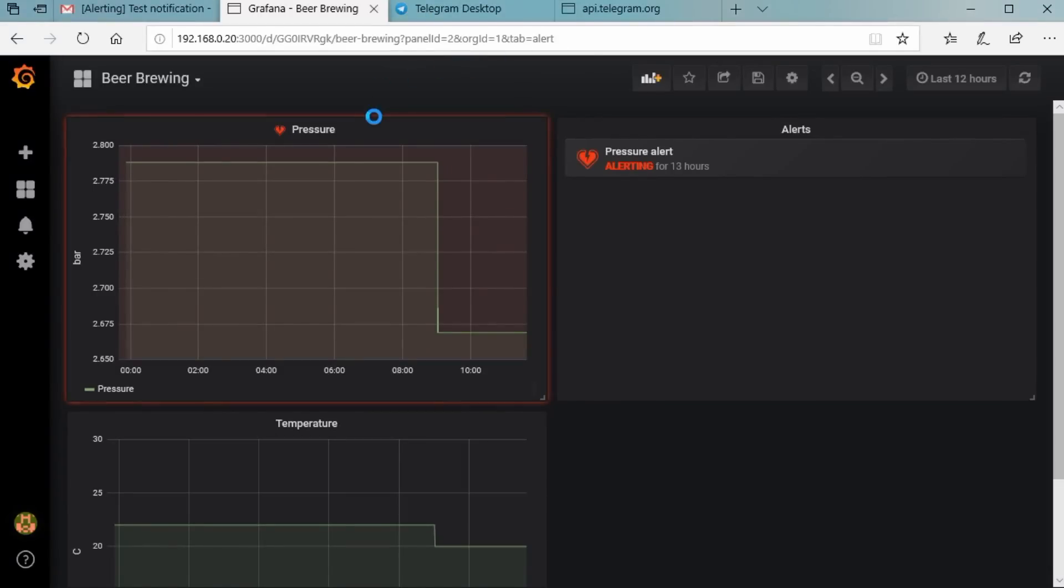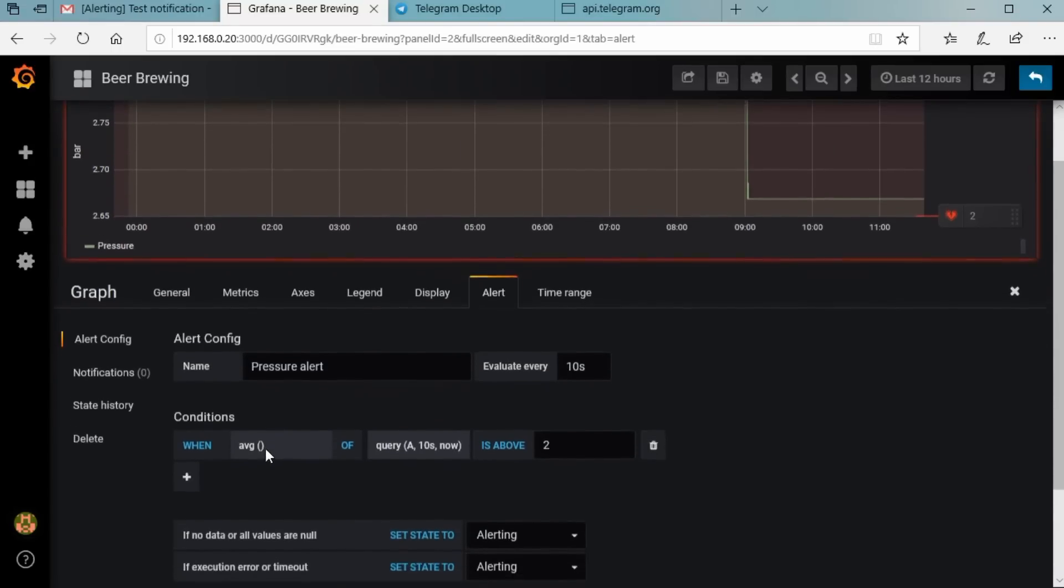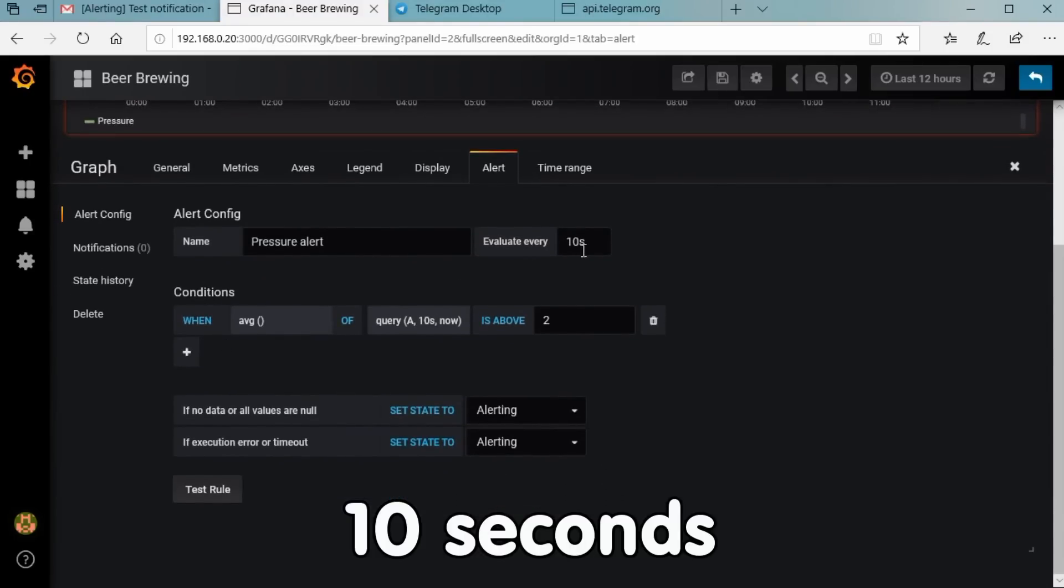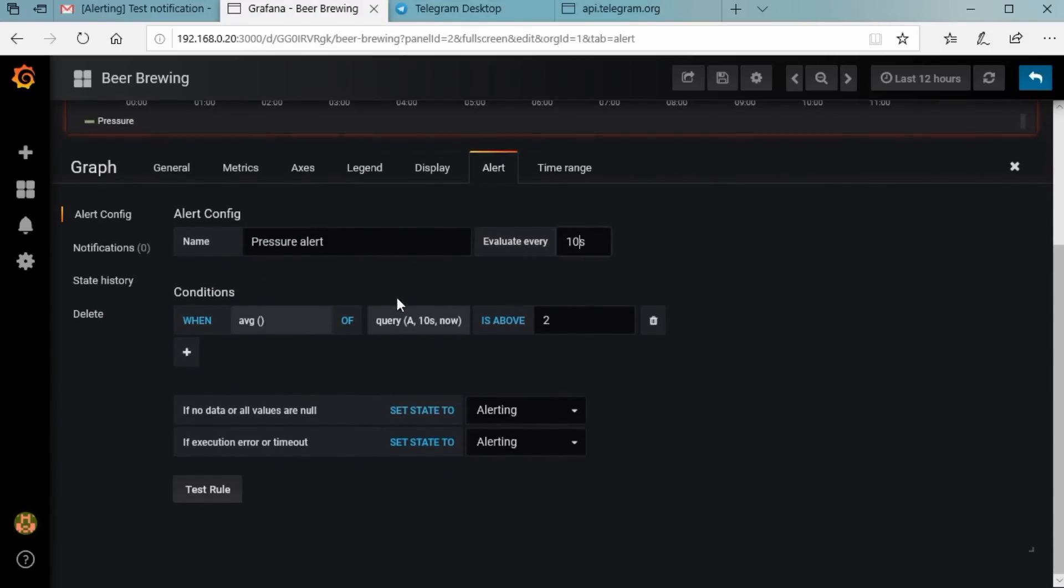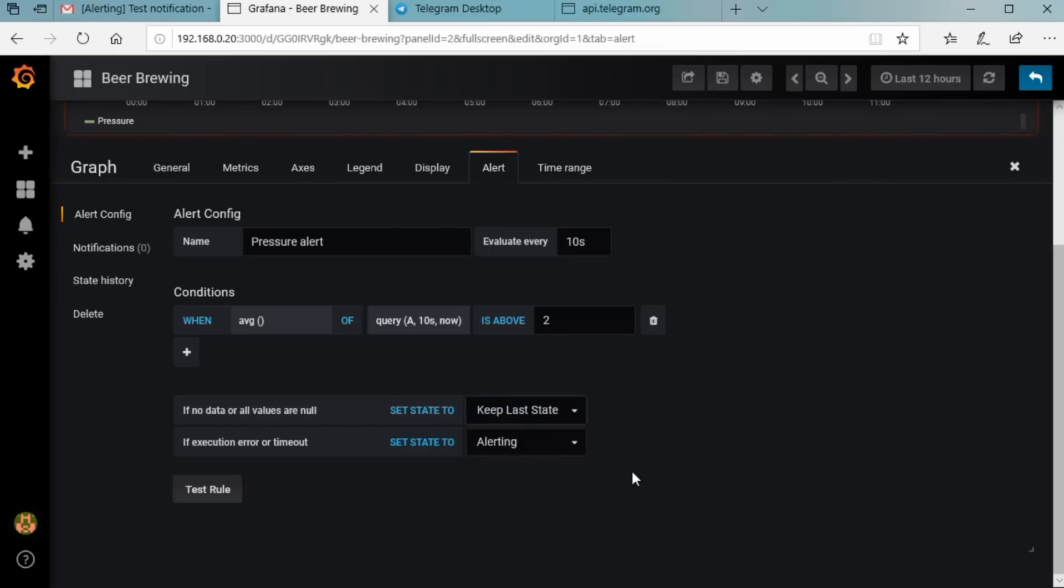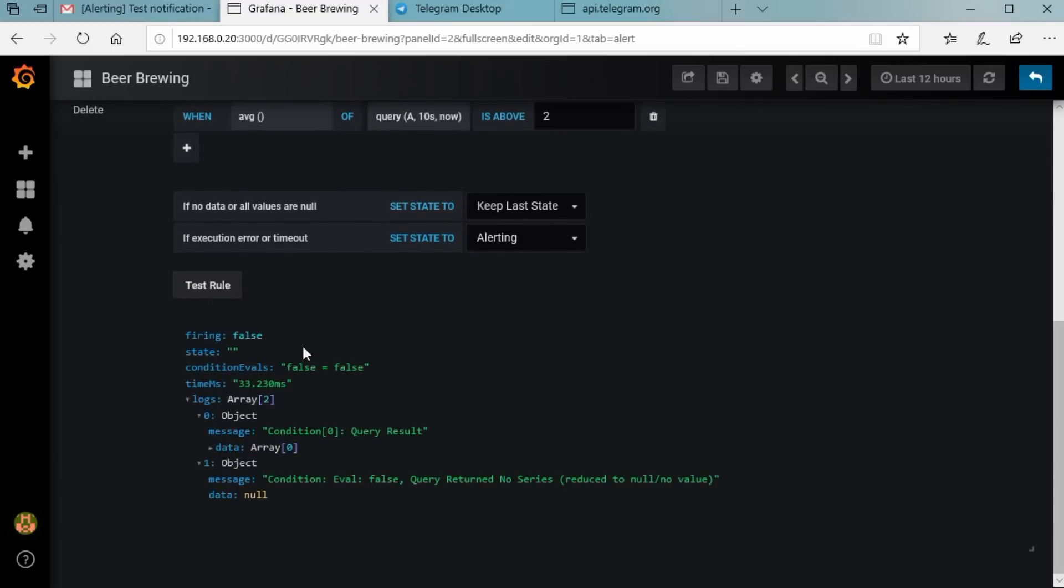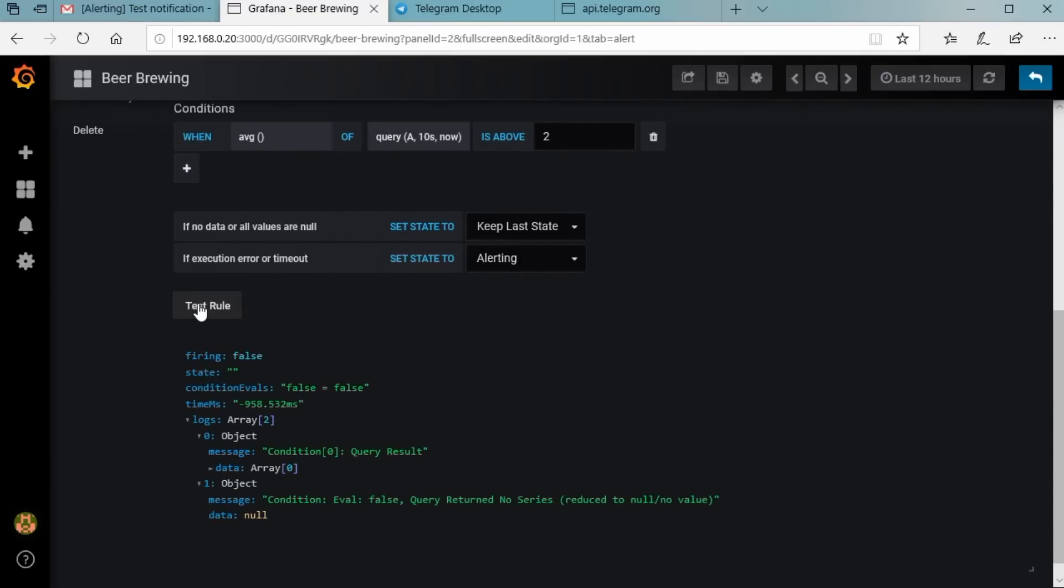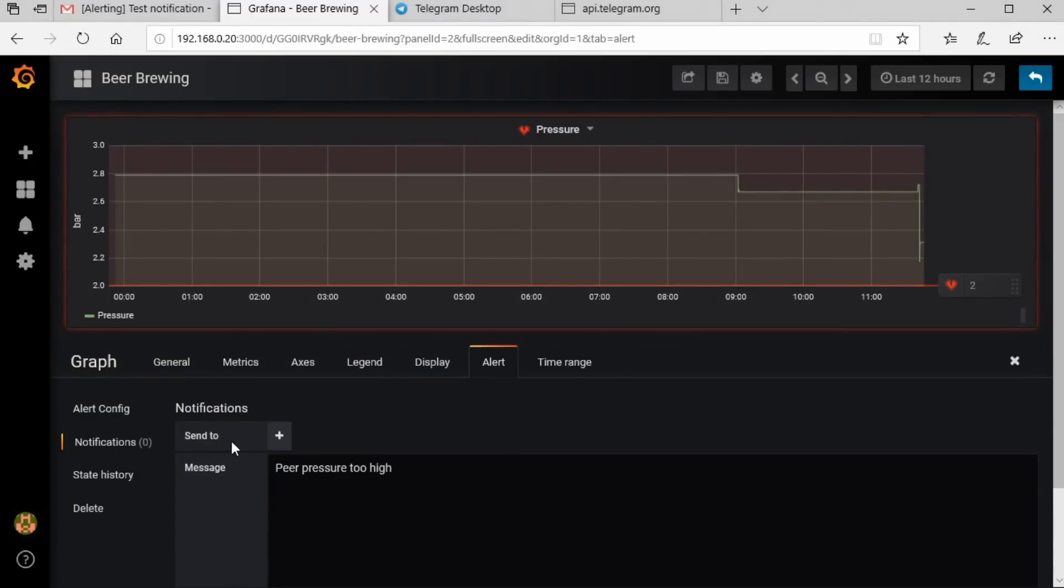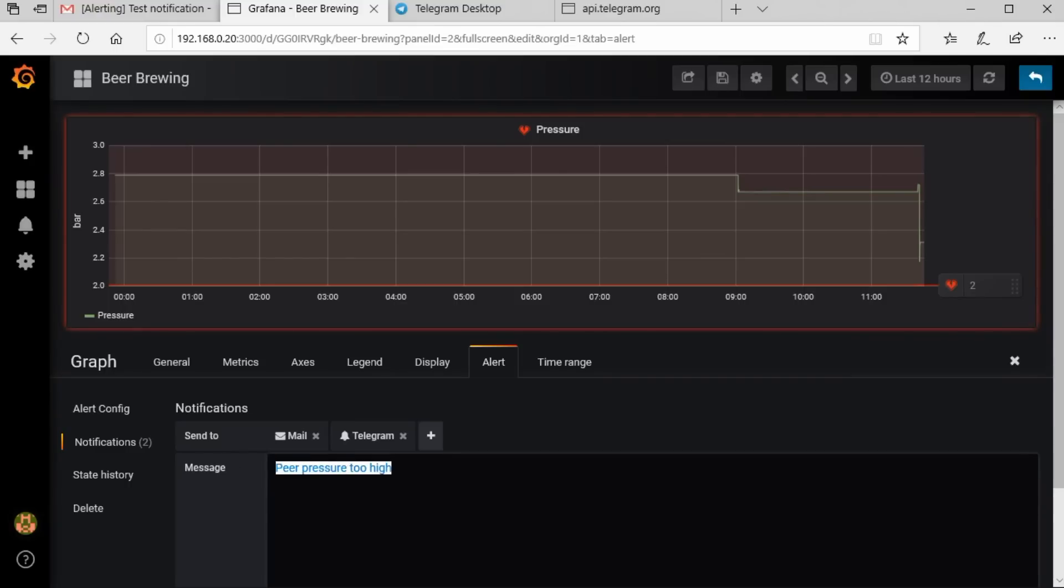But when do we want to be alarmed? This is defined in the alert rules. We edit the pressure dashboard and add the alert. It should be checked every few seconds and the alarm should be sent if the last value is above 2 bar. We also can define what to do if we have no data available or if the data is zero. We could decide to send an alert if no data was transferred. Because we know that our sensors only deliver values if the pressure changes, we choose last and test the rule. It evaluates false because the pressure is below 2 bar. If we increase the pressure, the test evaluates true. If we add our two notifications and a message, we should get alarms on our smartphone and in our inbox.